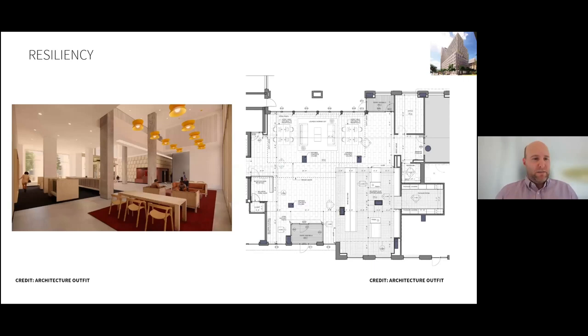Like 2050, Cooper Park also, as a large building, requires an emergency backup generator. And through the Buildings of Excellence Award, the team is reviewing an option to add an automatic transfer switch to the emergency system that will allow additional non-required convenience electric loads on the generator without increasing the size of the generator. Currently, the option would add electrical outlets and heating and cooling to the double height entry lobby and lounge of the ground floor and would provide conditioned air and an opportunity to charge devices in a power outage.